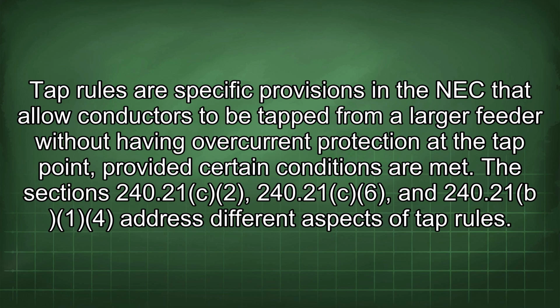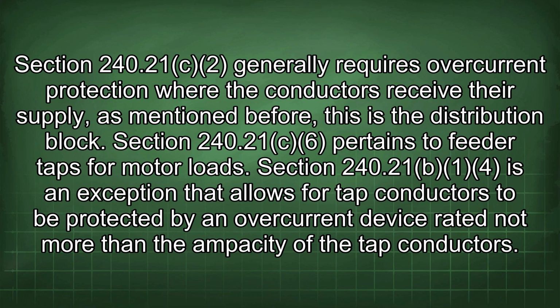Tap rules are specific provisions in the NEC that allow conductors to be tapped from a larger feeder without having overcurrent protection at the tap point, provided certain conditions are met. The sections 240.21(C)(2), 240.21(C)(6), and 240.21(b)(1)(4) address different aspects of tap rules. Section 240.21(C)(2) generally requires overcurrent protection where the conductors receive their supply, as mentioned before. This is the distribution block. Section 240.21(C)(6) pertains to feeder taps for motor loads.